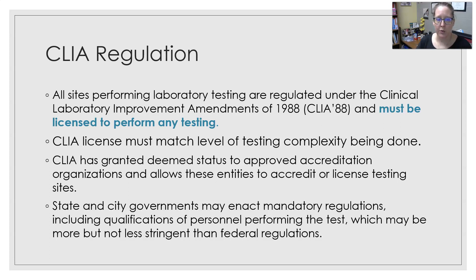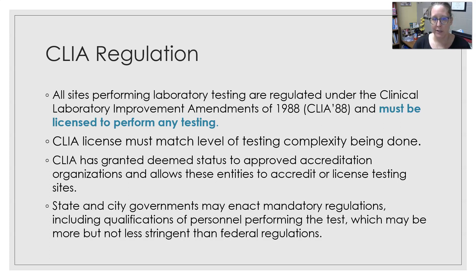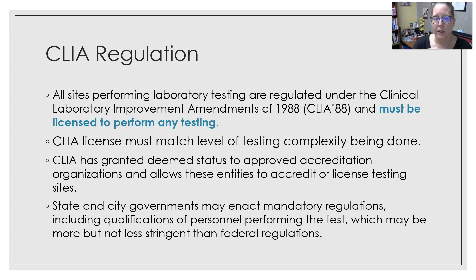Inspectors will verify that the CLIA license matches the level of testing complexity being performed by that lab. CLIA has also granted deemed status to different approved accreditation organizations, which can come and accredit and license testing sites. State and city governments can also enact mandatory regulations that are state- or city-specific, including qualification of personnel performing the test. These can be more stringent but never less stringent than federal regulations — CLIA is the minimum standard. For example, a state could require that only lab techs with a bachelor's-level degree perform high complexity testing.